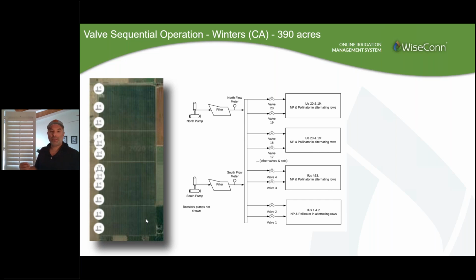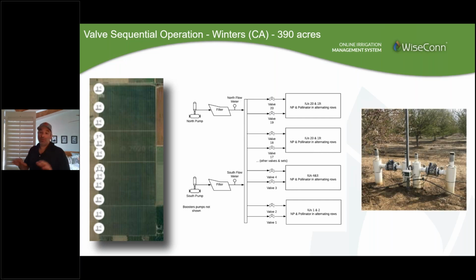And the velocity of the water, the pipes being big and how it was designed, basically had pressures going all over the place. So what would happen is that the operator would start the pump, open the first 4 valves of the block, and then when he needed to change the set, he would open the other 4 valves and then go and close the first 4. So what started to happen in those cases is that the pressure would drop, the VFD would ramp up, the velocity of the water would go higher, and it would take up to 30 minutes to go back to a regulated pressure on the main on the whole system.